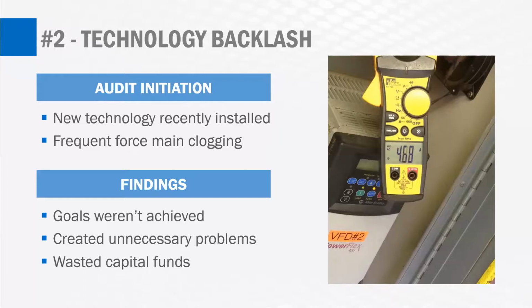The VFDs can really be utilized very well to achieve electrical cost savings, but it needs to be done in a planned and thought out process. The reason for the audit to be initiated was that there was frequent force main clogging occurring at the stations where these VFDs were installed. And it was starting to become a real head scratcher of what was going on here. So audits were performed, and digging really far into the details to try to come up with the issue, it turns out there was a mistake made in the controls logic for these variable frequency drives.